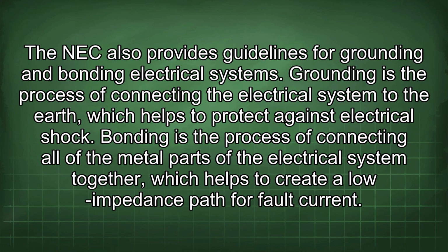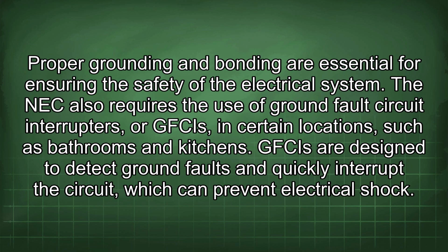voltage drop. The NEC also provides guidelines for grounding and bonding electrical systems. Grounding is the process of connecting the electrical system to the earth, which helps to protect against electrical shock. Bonding is the process of connecting all of the metal parts of the electrical system together, which helps to create a low impedance path for fault current. Proper grounding and bonding are essential for ensuring the safety of the electrical system. The NEC also requires the use of ground fault circuit interrupters, or GFCIs, in certain locations, such as bathrooms and kitchens. GFCIs are designed to detect ground faults and quickly interrupt the circuit, which can prevent electrical shock.